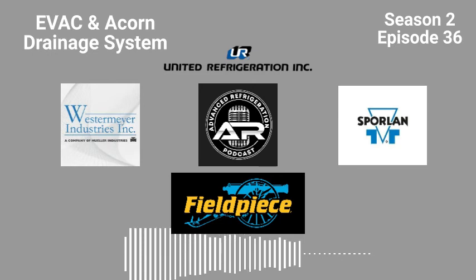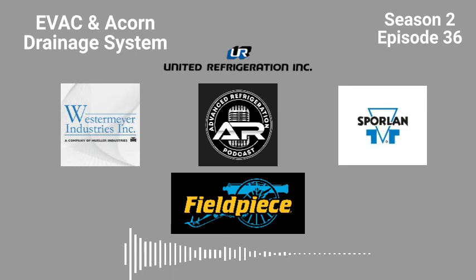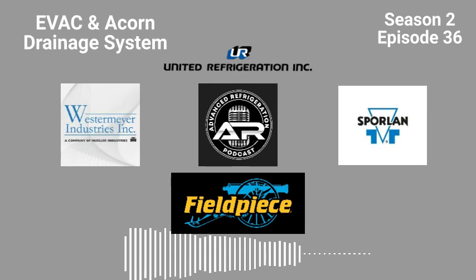That's the electricians. I never had this happen in 10 years until like last year. I walked into a store for startup, and all the fitters were gone for a week because we were so far ahead of everybody. Every single evaporator coil was trimmed out and ready to go. And I look, and I'm like, oh, my God. They mounted the electrical boxes right to the bottom of the evaporator, shot a nipple through it, and brought all their wire through the bottom of the evaporator and on the pan. Then I went to another job. Same thing happened. It was like a rash of them for a month.